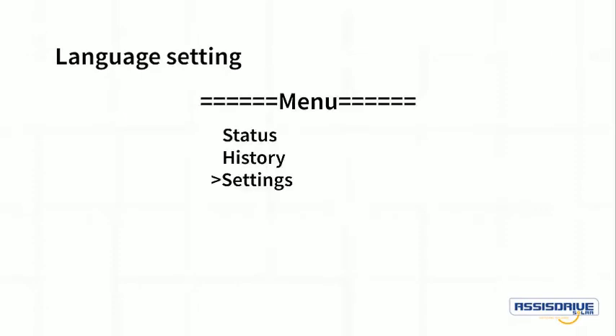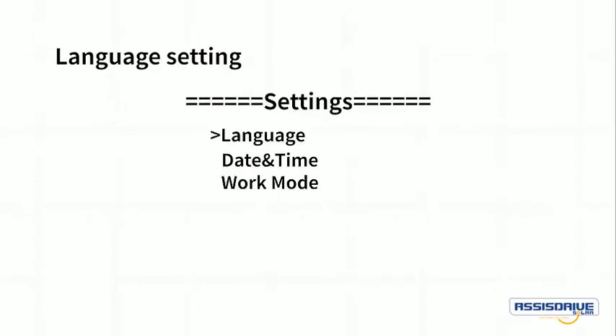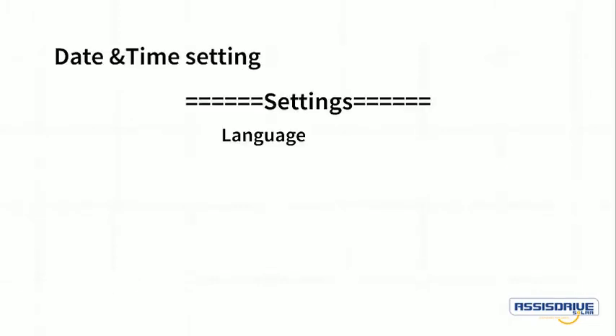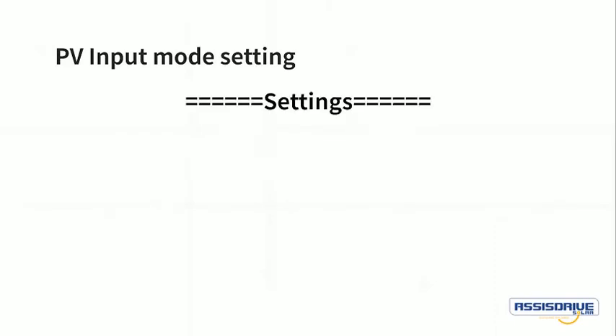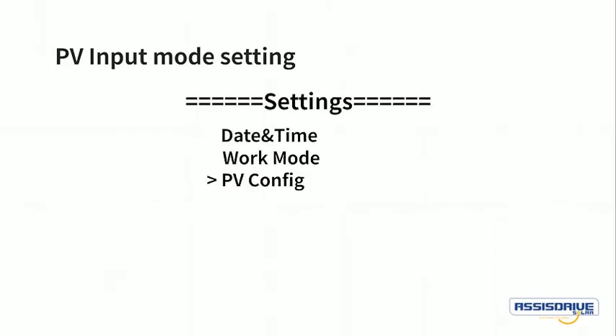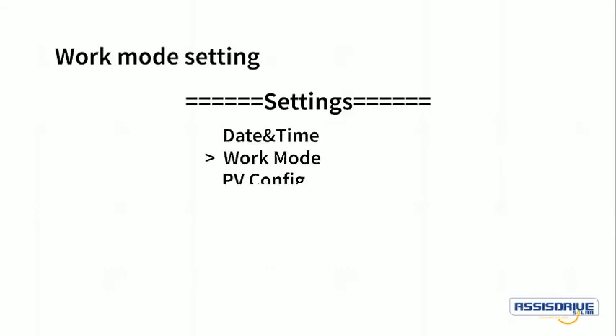Language setting. Press the Enter key to enter the main menu, Settings, Language, and select Language. Long press enter to confirm the setting. Date time setting, select date time to set the time and date of the inverter, long press the enter key to confirm the setting. PV input mode setting, select PV config to set the PV input mode of the inverter, long press the enter key to confirm the setting. Work mode setting, select work mode to set the inverter's work mode, long press the enter key to confirm the setting.